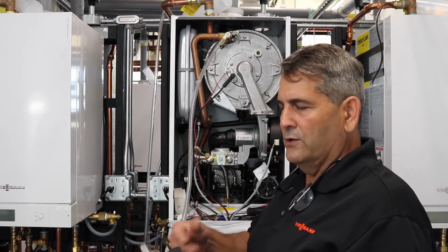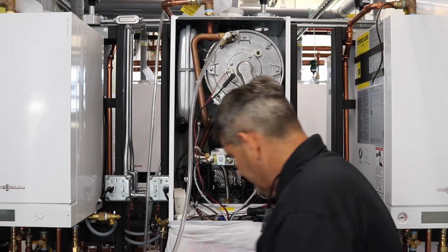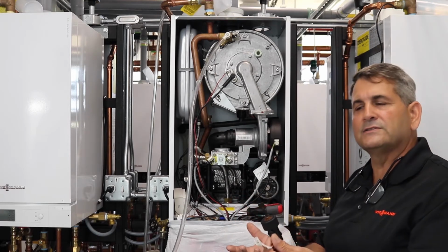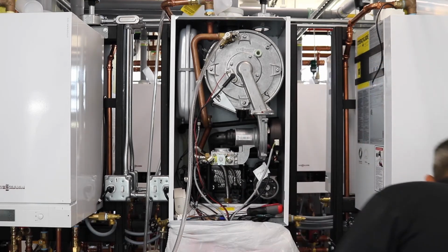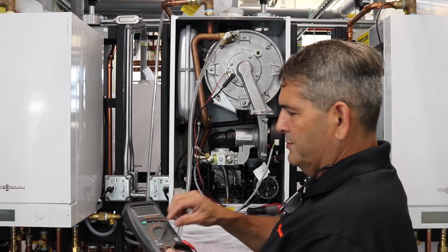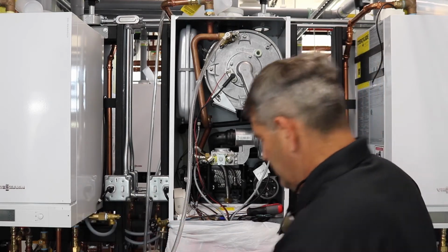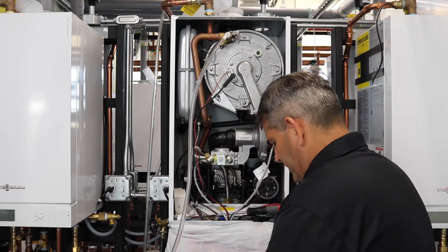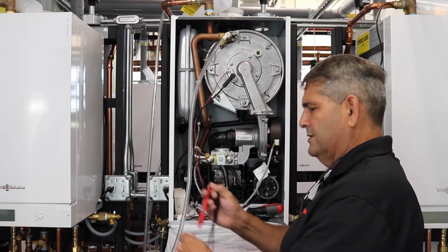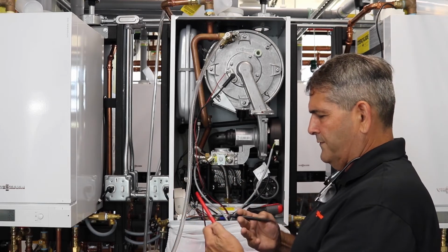As soon as we pull it out, we check for continuity again, which is just another way of checking to see if this opens or closes and make sure that it's still functional. So what we would do in that case is take our meter and put it on audible sound, on ohms, and hopefully you have clips for this test, so you can test it by holding it onto each probe itself.